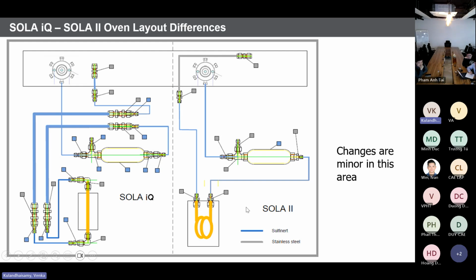So when you compare to SOLA 2, the SOLA IQ is very easy to maintain. Meaning, if you want to change the tube from the pyrolyzer, SOLA 2 is a little difficult because it is made of pure silica, so it is easily fragile. You have to take care when you are replacing this tube. But in SOLA IQ, it's a ceramic tube, which is not very fragile. You are able to replace the tube very easily. So that is one improvement from SOLA to SOLA IQ. The rest are all the same.